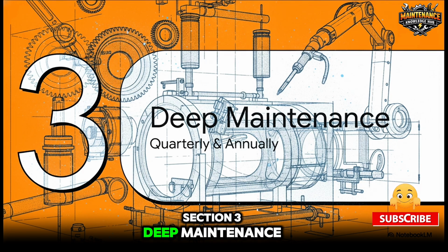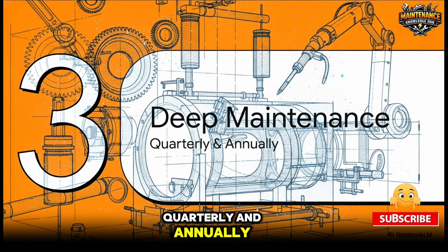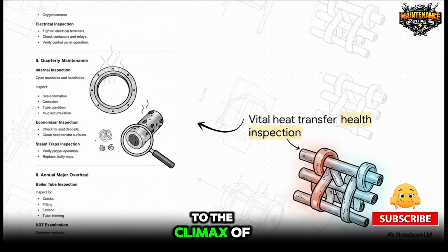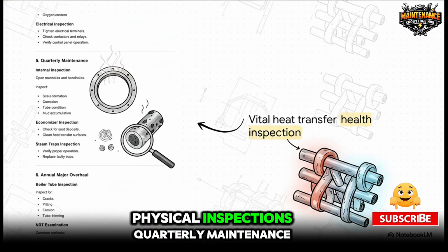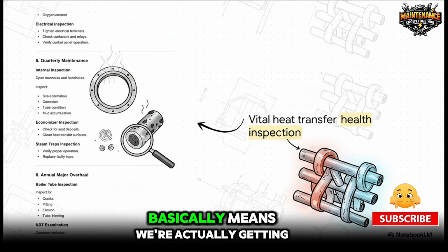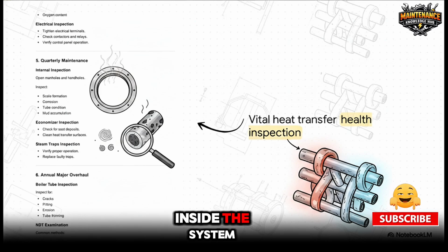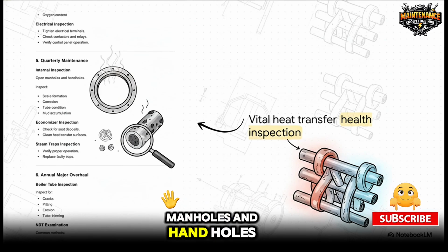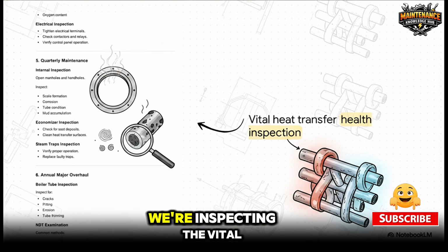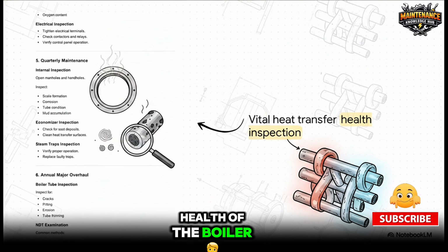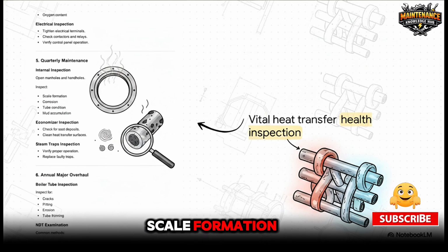All right, let's get into the heavy stuff. Section 3, Deep Maintenance, Quarterly and Annually. Now we're shifting gears to the climax of the routine, breaking out the heavy machinery concepts for deep, physical inspections. Quarterly maintenance basically means we're actually getting inside the system. You're opening up those manholes and handholes. And what are we looking for? We're inspecting the vital heat transfer health of the boiler. We are hunting for scale formation.